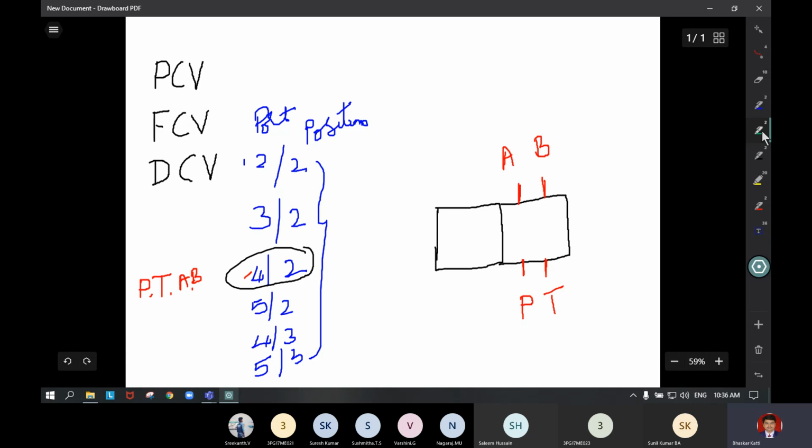So now first we will write the flow path. Before activating the valve, it is usual practice that the pressure should be connected to the rod side, so that the cylinder does not extend upon switching. So P should be connected to the B port, as the B port is usually connected to the rod side of a double acting cylinder.